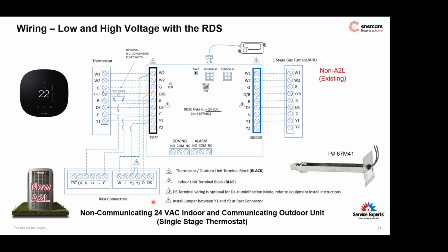Any thoughts? Any questions? Essentially, if you don't have that sensor, then do not hook up that wire. Probably not a great idea. That's right. Otherwise, you'll end up cooking the compressor in your brand new A2L heat pump because you're taking on too much heat in your refrigerant and bringing it back to the compressor to be pumped. Damage can be done.